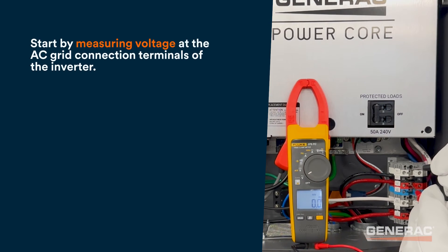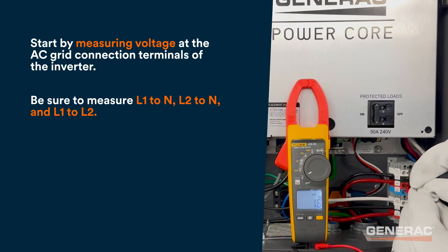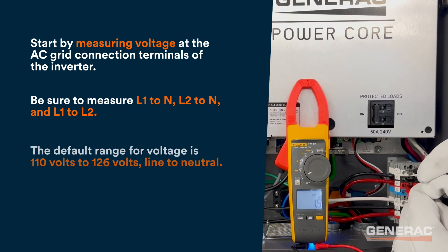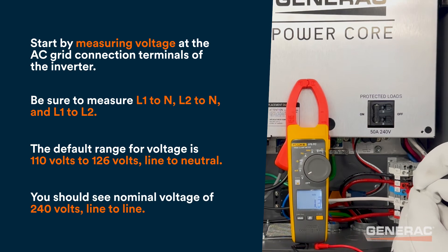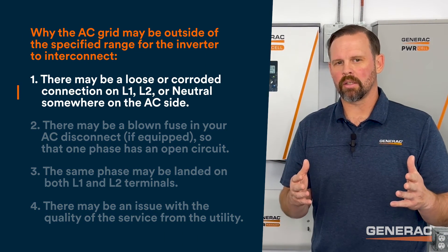Start by measuring voltage at the AC grid connection terminals of the inverter. Be sure to measure line 1 to neutral, line 2 to neutral, and line to line. The default range for voltage is 110 volts to 126 volts line to neutral, and you should see a nominal voltage of 240 volts line to line. If voltage is drastically low or non-existent when measuring line to neutral or line to line, you likely have a faulty connection.